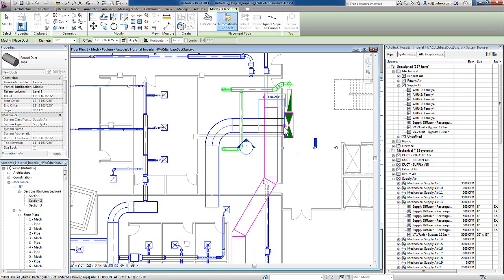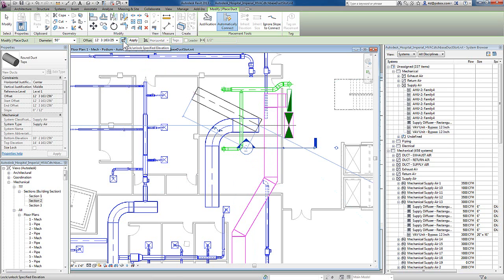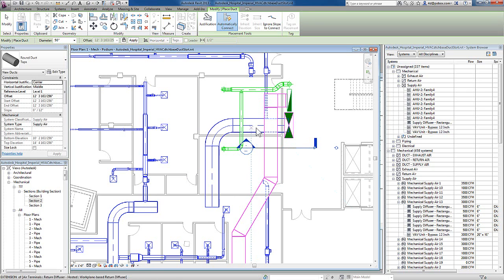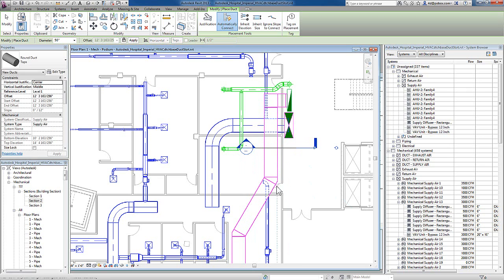As I'm transitioning to a vertical duct, I do want to move to the options bar and lock the elevation down. That way, when I pick this duct, it doesn't try and pick the end point, which may be below or above. So, by locking the elevation, it automatically keeps this as one elevation rather than trying to connect to the top or the bottom of the duct that's in this chase.